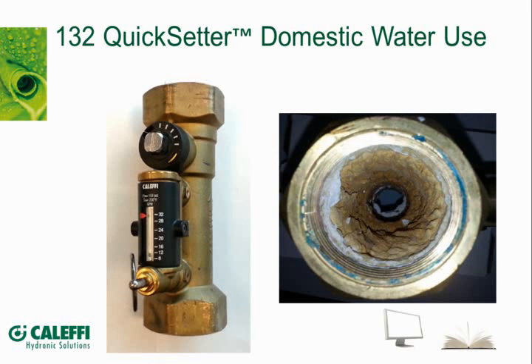Jeff, you mentioned that water, basic minerals, will precipitate out as a function of temperature. So the higher the temperature, the more problems you have with hard water. Is there any function as it relates to calcification of pipes regarding the velocity of the fluid traveling through it? I mean, is fast fluid more forgiving? Yes, faster is more forgiving, because a higher velocity in the pipes helps to, shall we say, erode or abrade or keep that scale from forming. So speed helps reduce the amount of scale formation inside the lines.